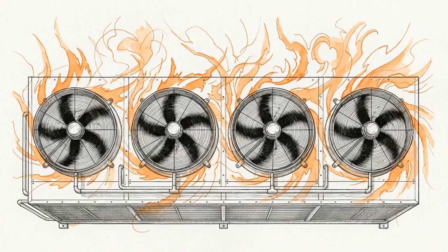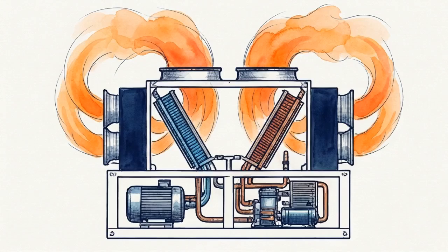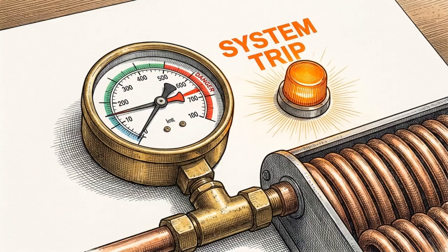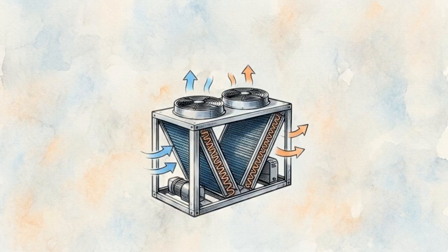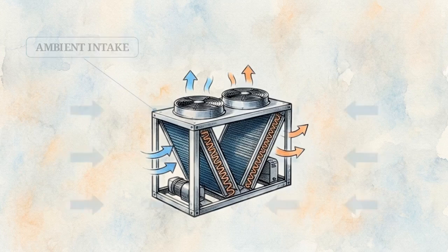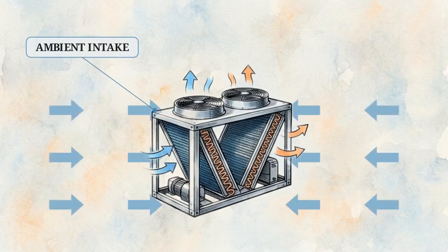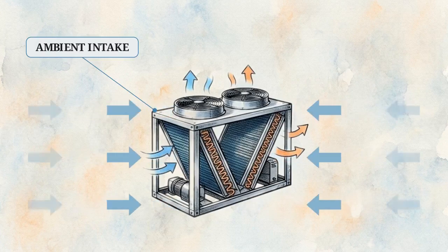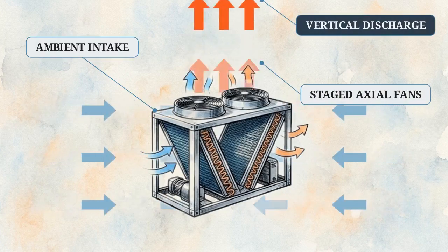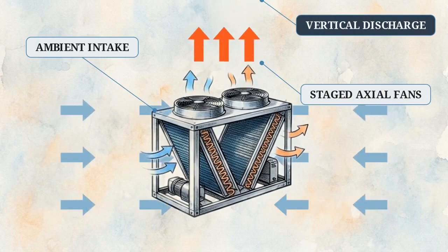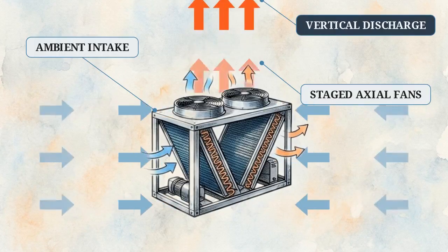If the system rapidly stages its condenser fans in extreme heat, it creates an aerodynamic risk. Hot exhaust air can be pushed down and recirculated back into the air intakes, rapidly spiking the condensing temperature and triggering high-pressure trips that shut the chillers back down. Proper physical plant design mitigates this recirculation risk. Units utilizing an open V-bank coil design and vertical heat discharge force the staged high-velocity hot exhaust air up and away from the equipment, preventing it from looping back into the intakes.